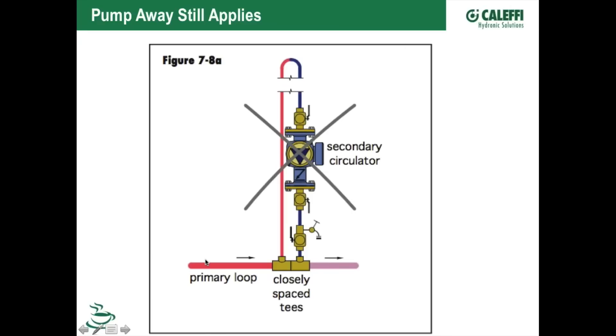Another primary-secondary mistake: pumping into the system instead of pumping away from the point of no pressure change established by the expansion tank. The secondary circulator needs to pump away from the hot side tee, out to the system, through the distribution, and back in. This isn't just a matter of flipping the pump direction — you'll need to physically re-pipe, moving the pump from the return side to the supply side.